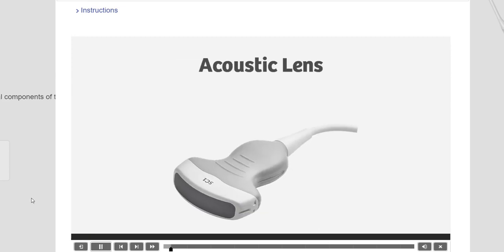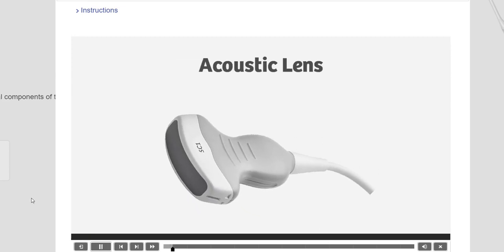The acoustic lens. The acoustic lens is a membrane cap displayed here as a large gray region. The lens is a cap that covers the elements. The lens acts as a mechanical separation for electrical isolation and cleaning the surface. The lens provides further focusing in the elevation plane. A common term for the surface of the lens is the footprint.